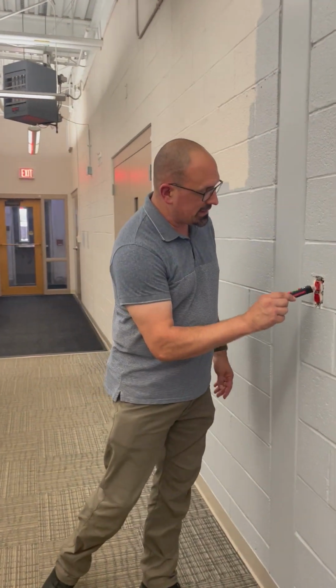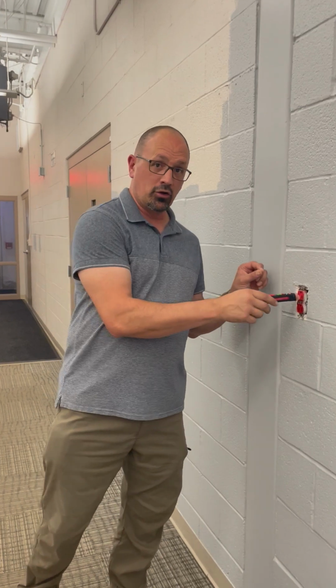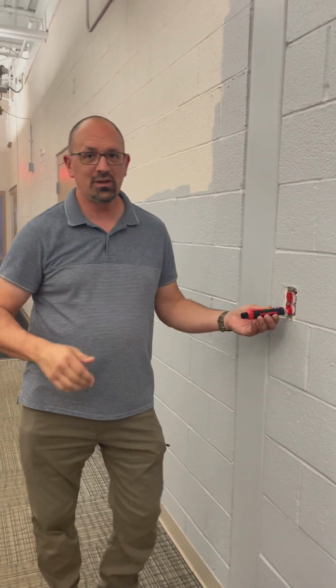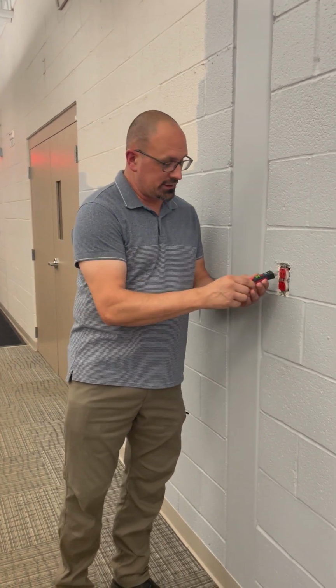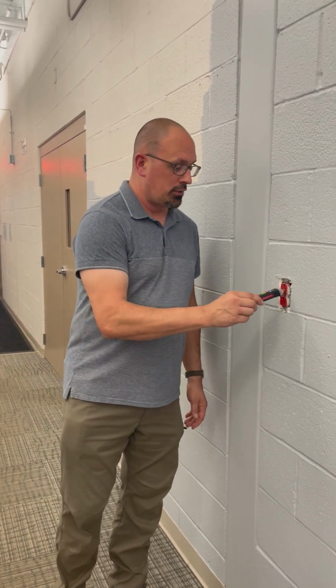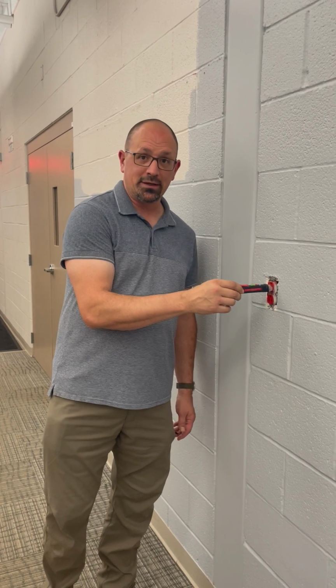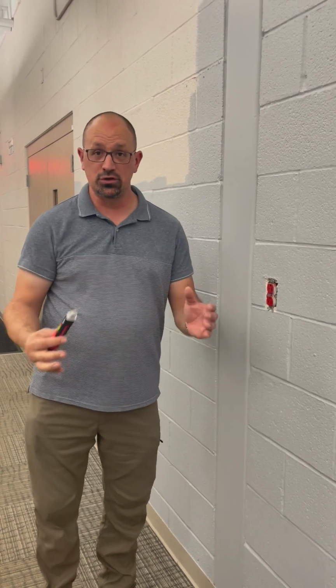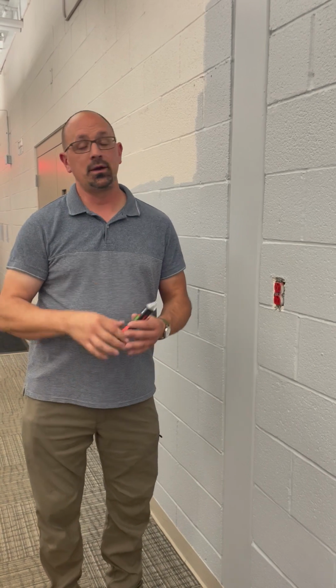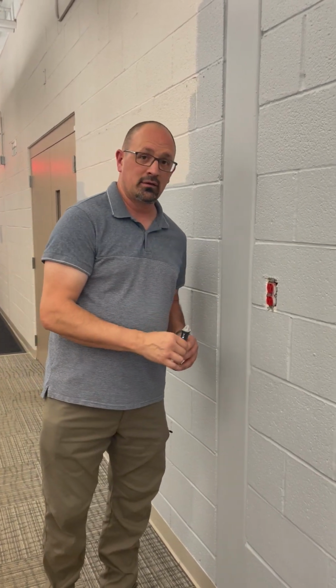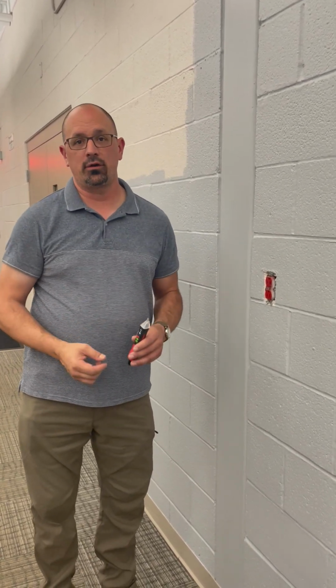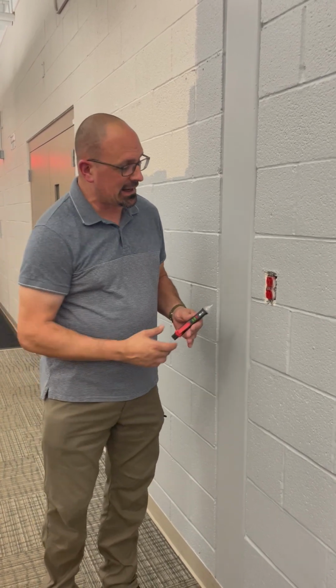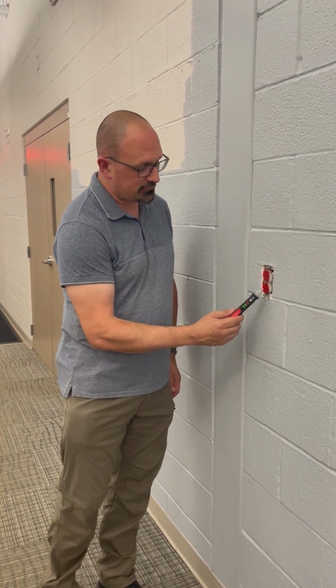So you always wanna make sure you go in the small vertical and test them. Now, here's the other thing: if you go into that small vertical and test and get no power, you're not done. Go and put it in the large one then. The large one is a neutral and you shouldn't get a reading. But don't ever walk up to an outlet and assume somebody wired it correctly, because they may not have. So you test every single one.